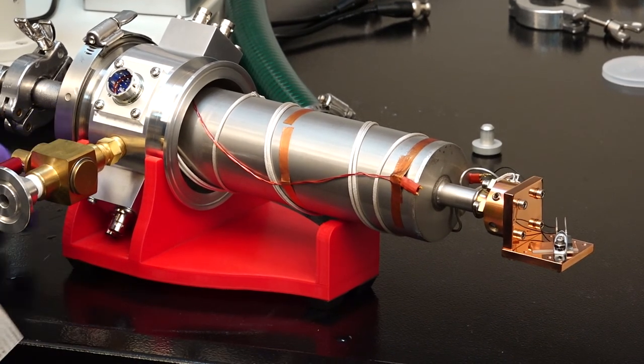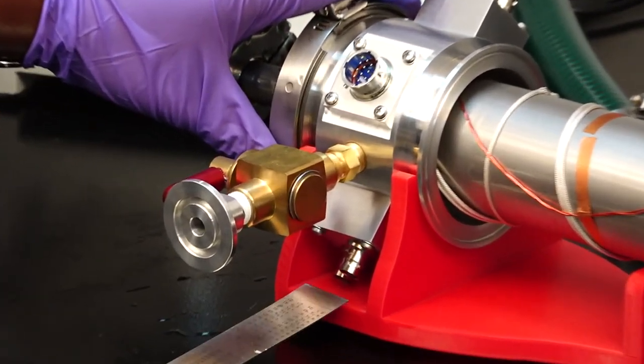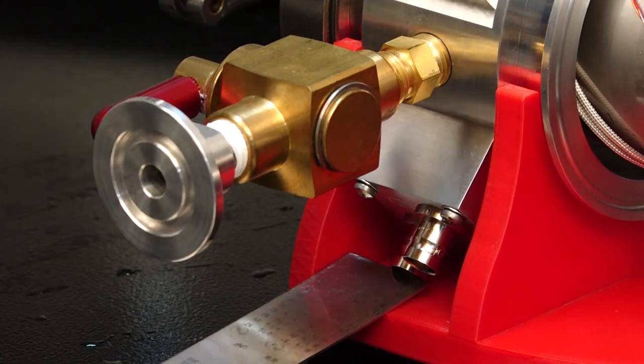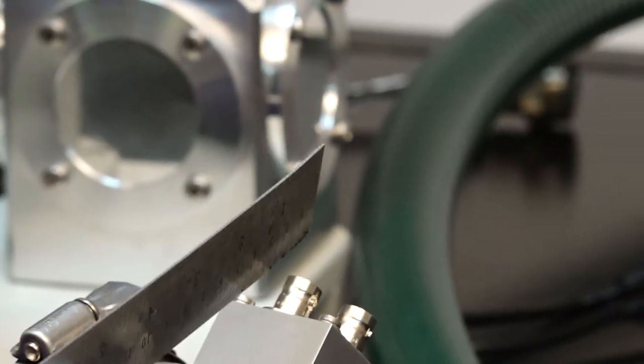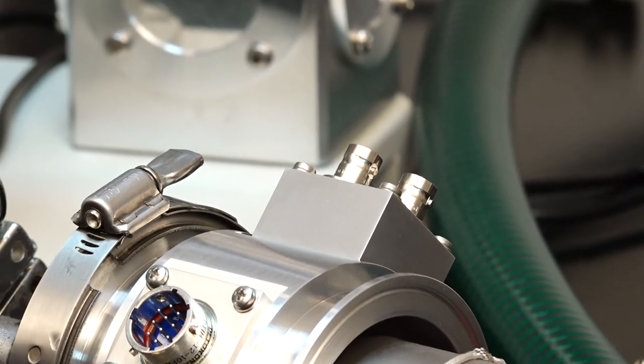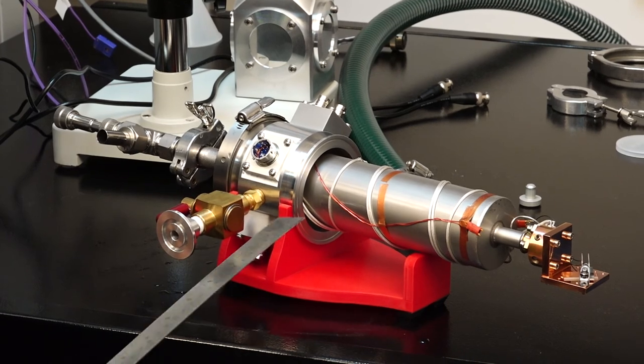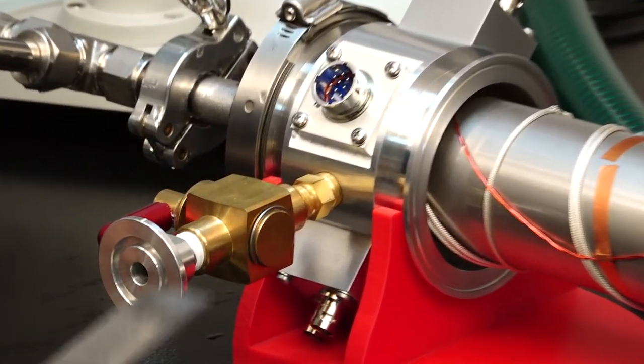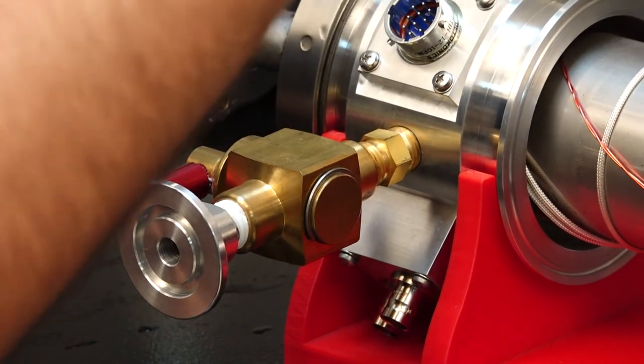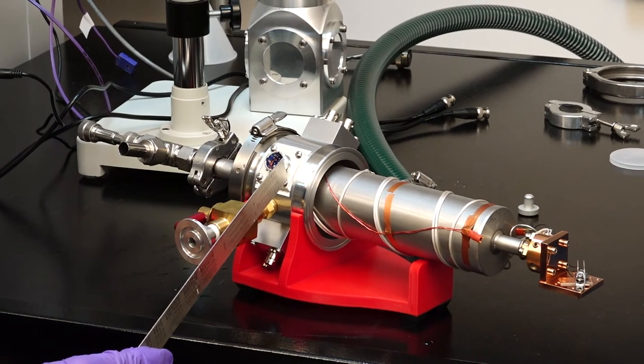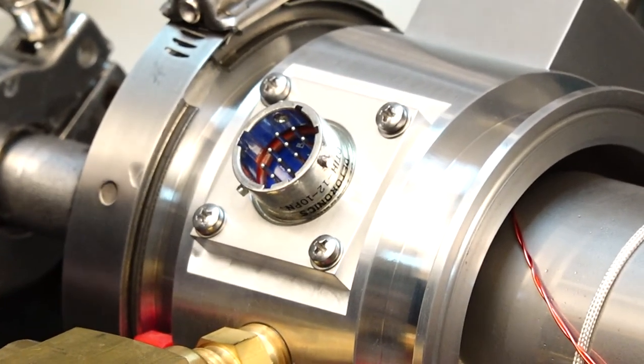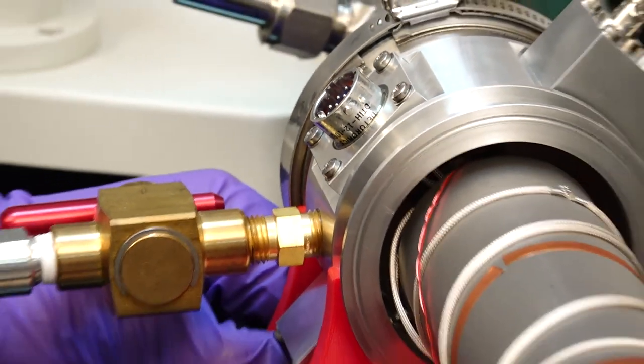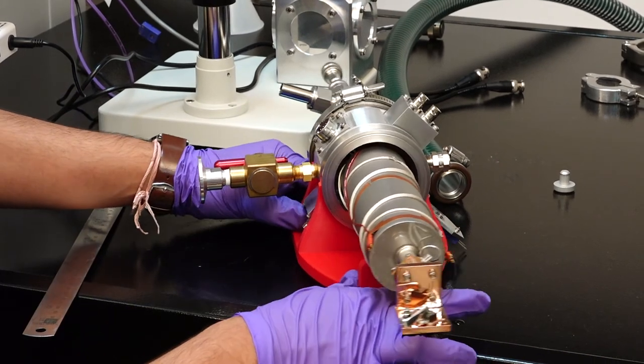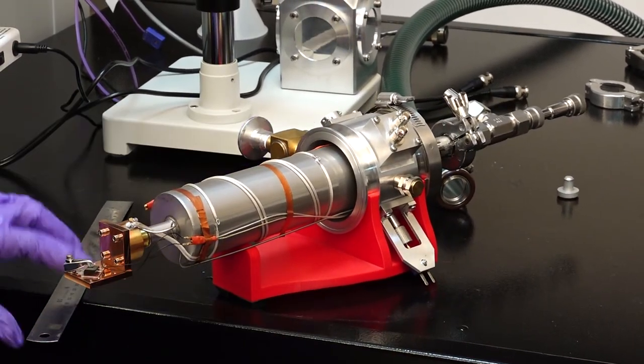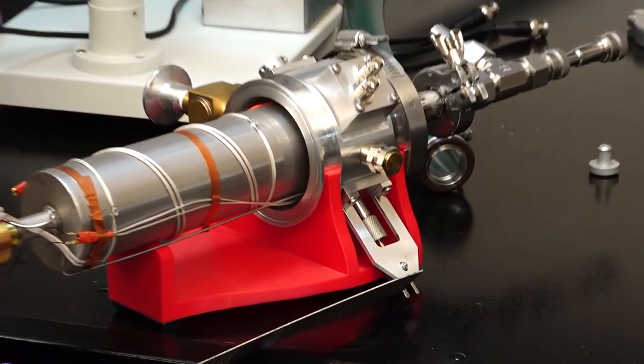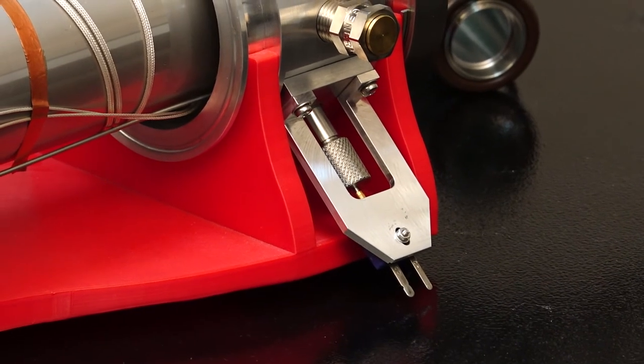So how do we apply the biases? For electrical bias, we have this BNC port here, which will be visible when the stage is put vertically. For LED connections, we have this BNC port here, which would supply power to the LED. Now to maintain chamber vacuum, we have this valve which connects to the turbo pump using a specialized cable. We have the temperature controller gauge connected here, which controls the heating stage. We have a thermocouple unit connected here, which gives feedback to the temperature controller for efficient and stable control of temperature.